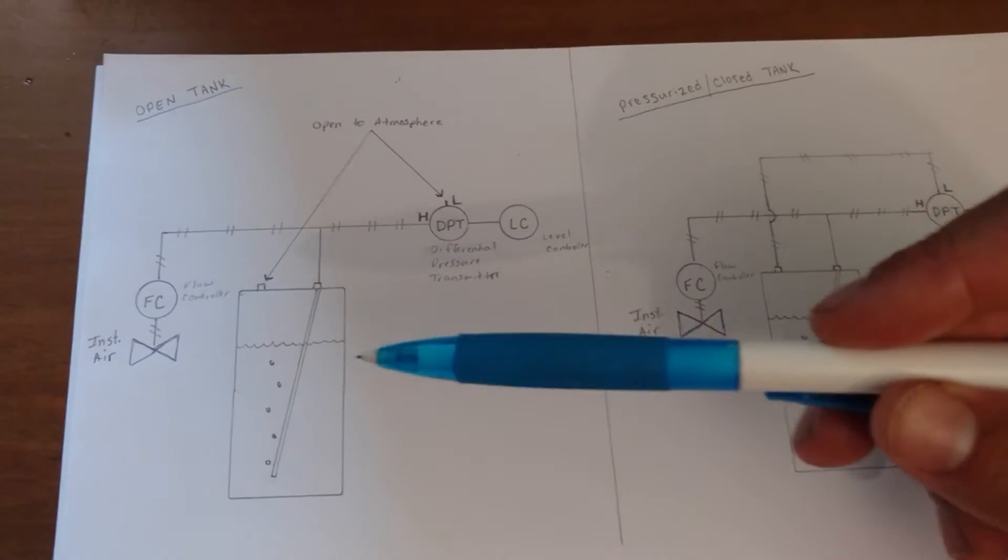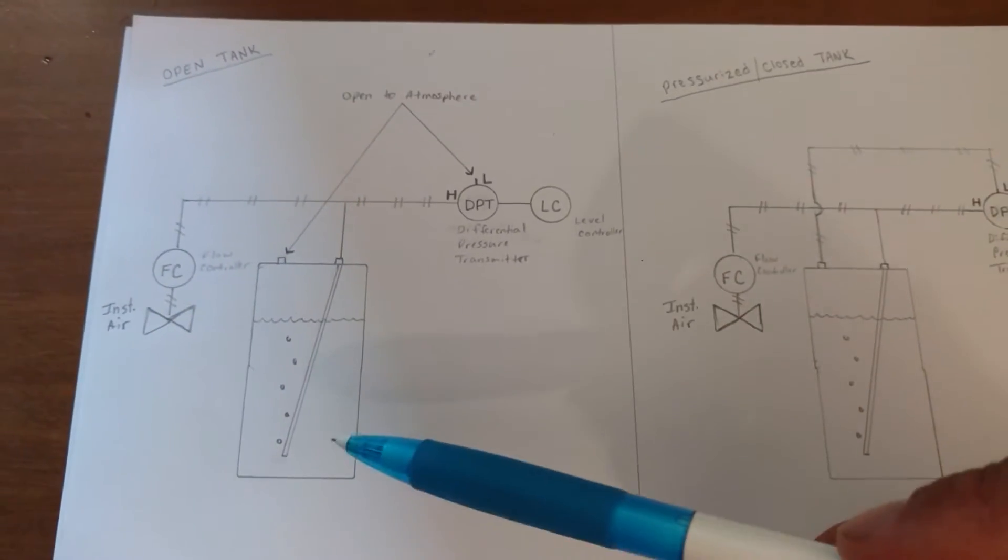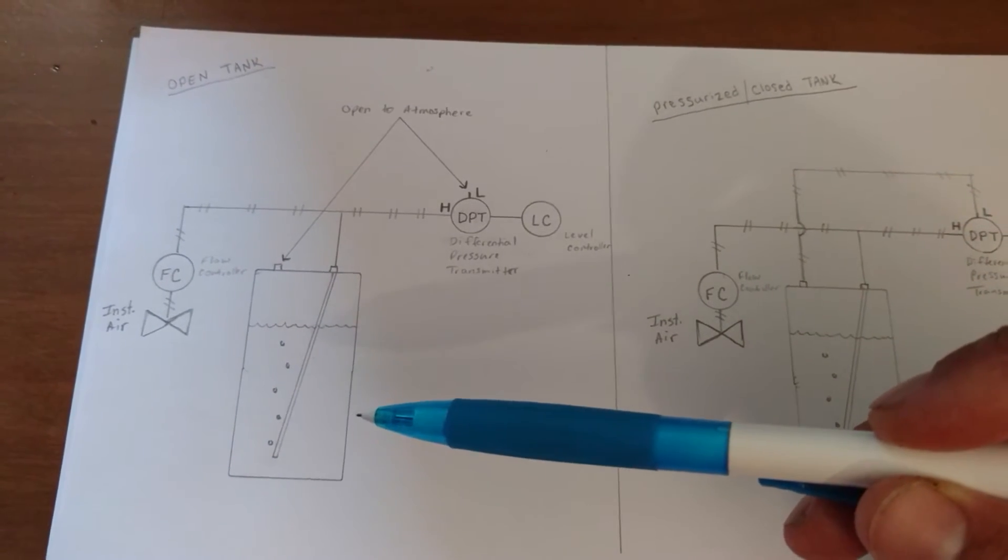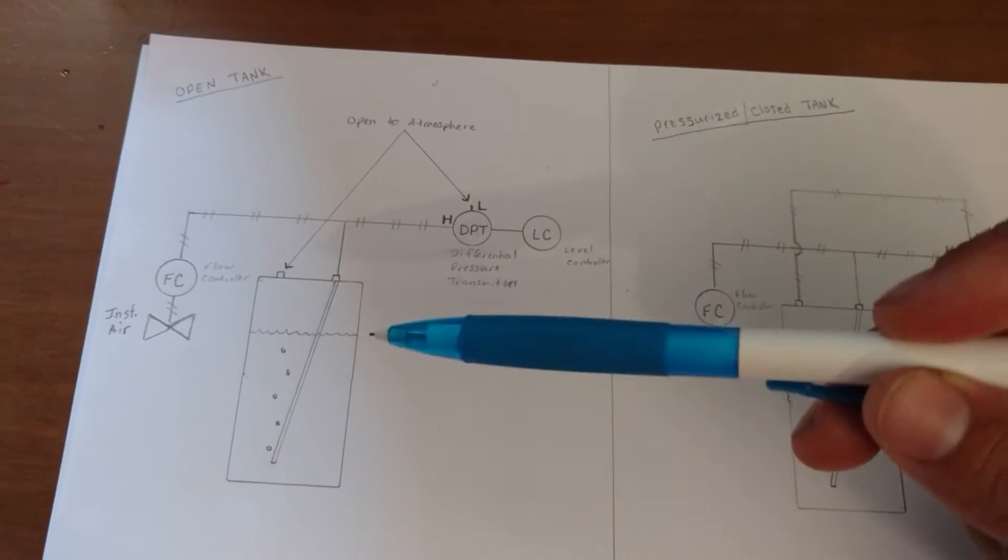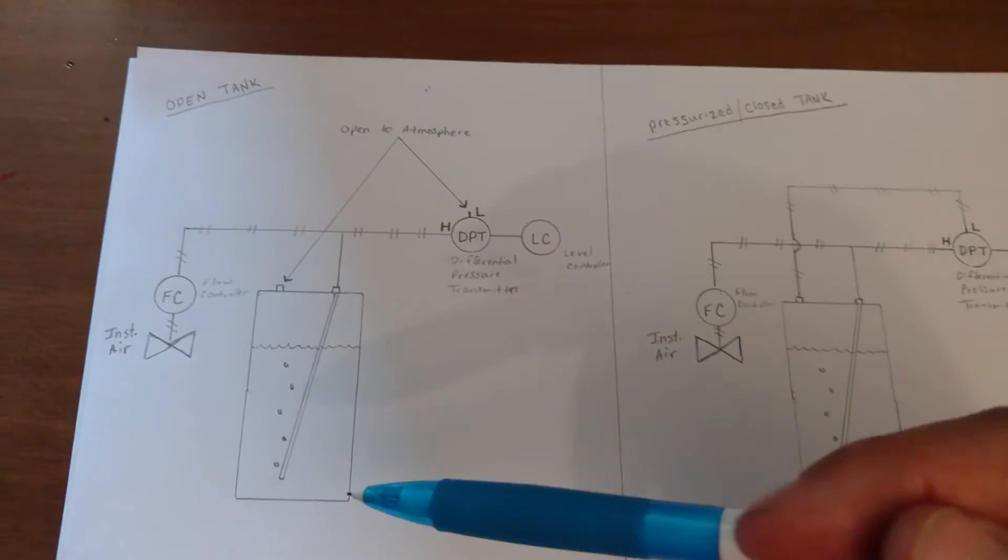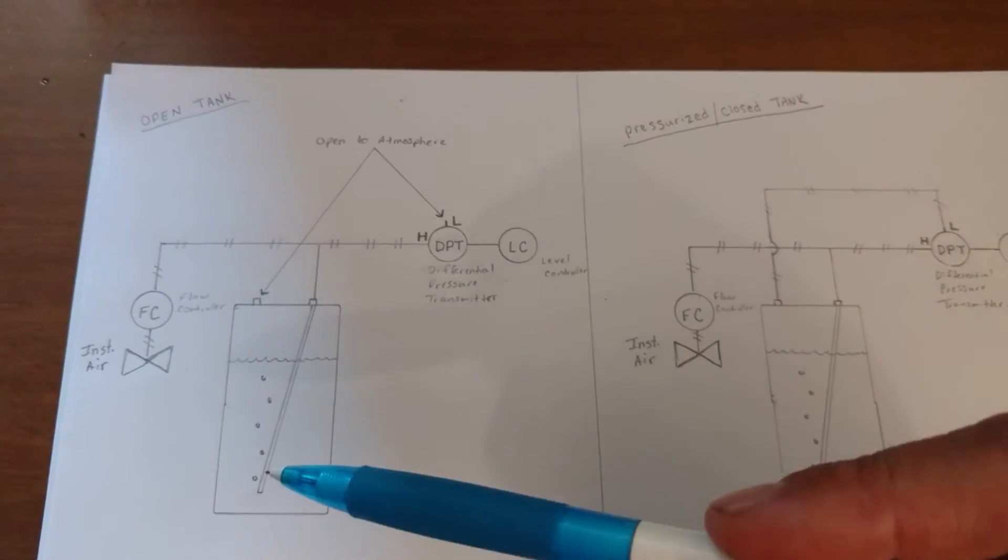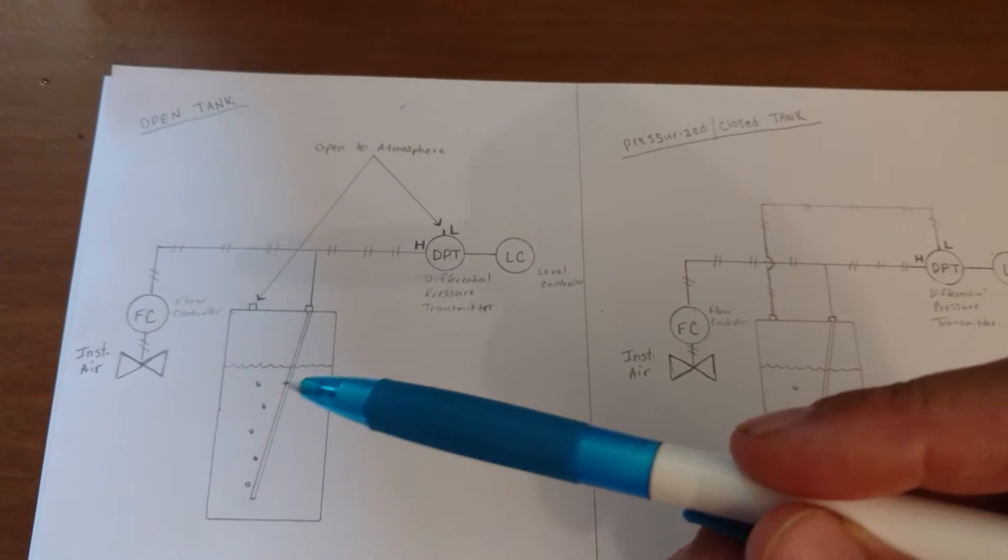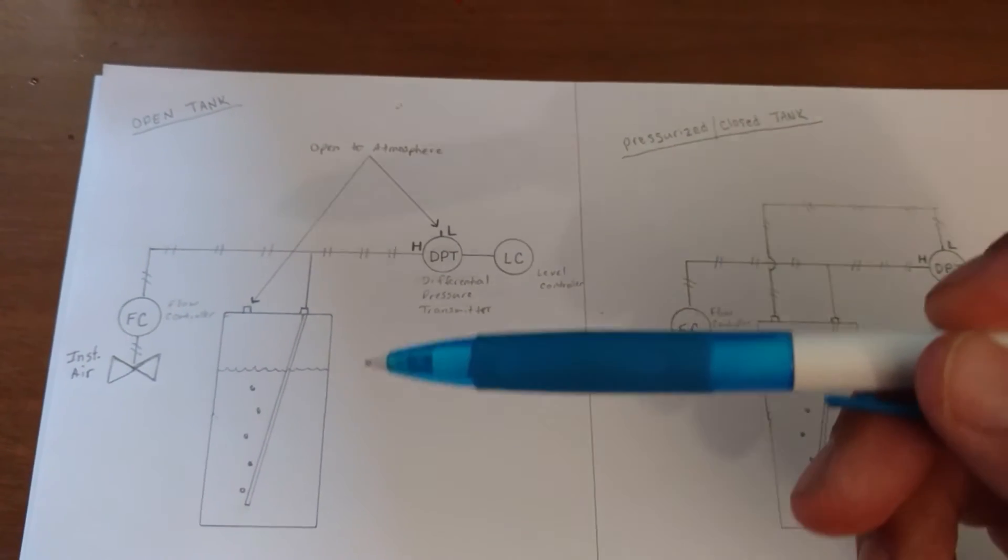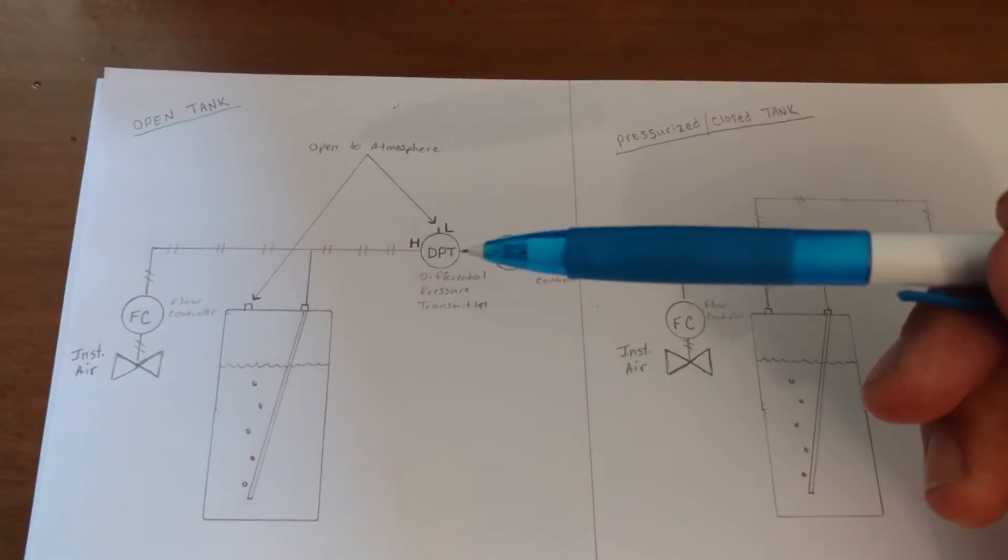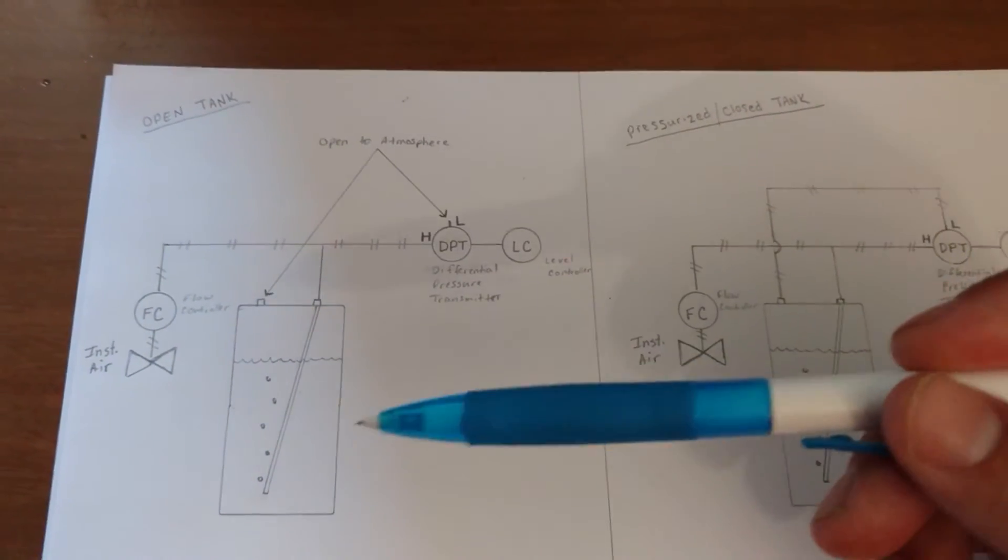What's happening here is as the level of your container is filled with water or increases in depth, the pressure that's going to be needed in order to force these bubbles or force air out of this tube is going to increase. And based on this increase in pressure, we can find the level of our tank.